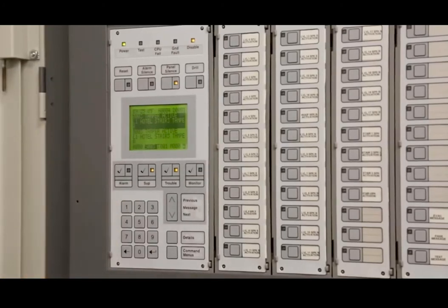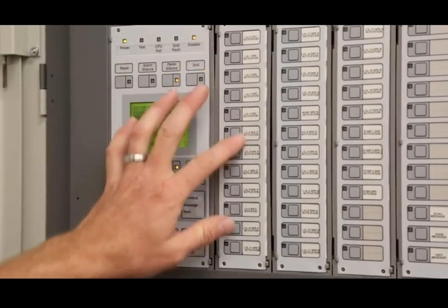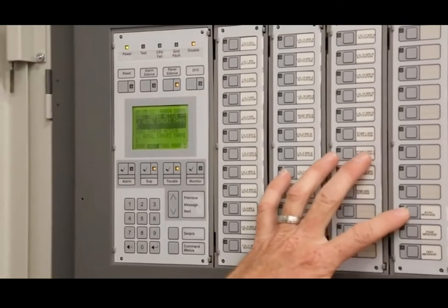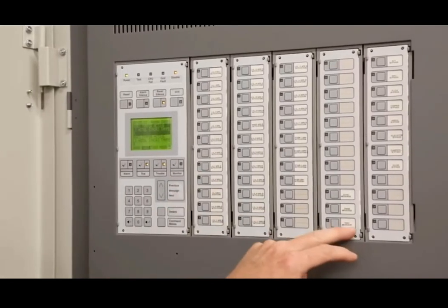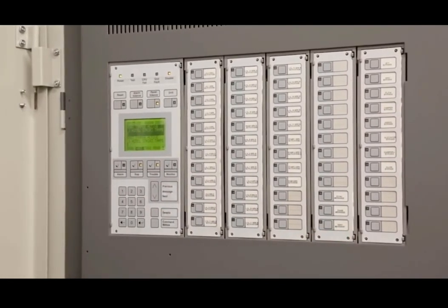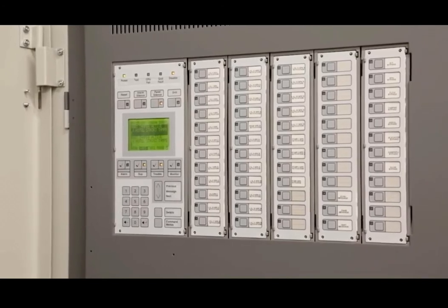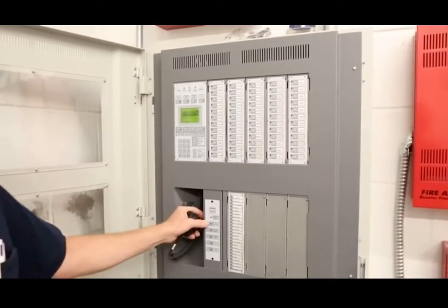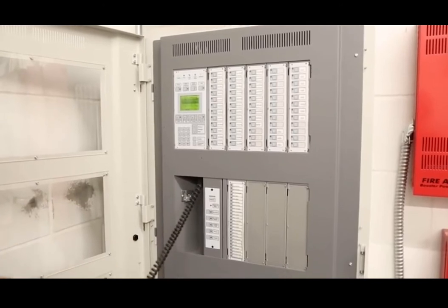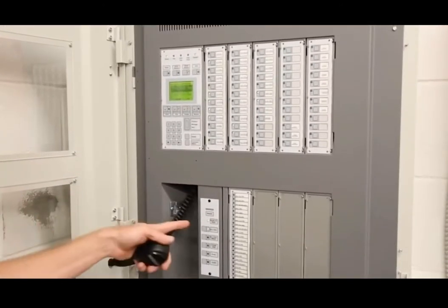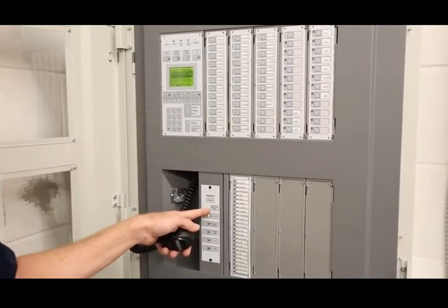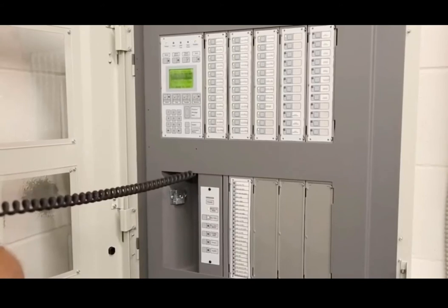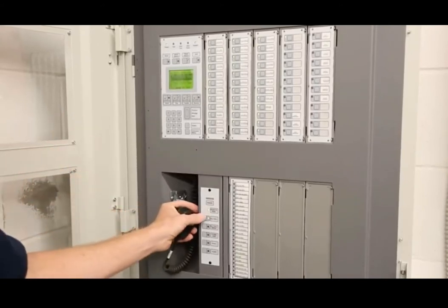I guess if we wanted to do an announcement, we can select the button here. You can hit page message and select what floor you want to go to. Or we have a test message for when doing testing or evac. Or if you want to talk to everybody on every floor, basically hit all call right here. Key the mic. Wait till that's picked. You notice all these lights are lighting up, everything's picked right now. Test 1, 2, 3, so it's going through the whole place. It doesn't set an alarm first? No.